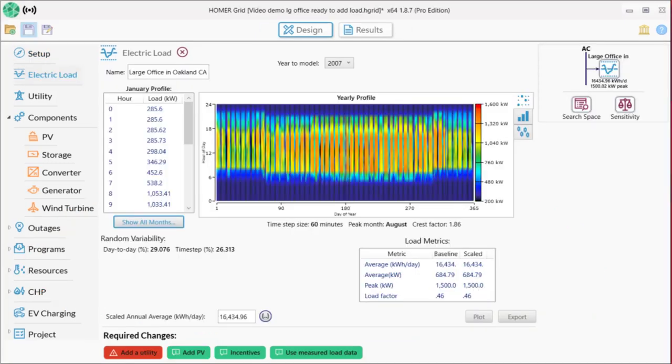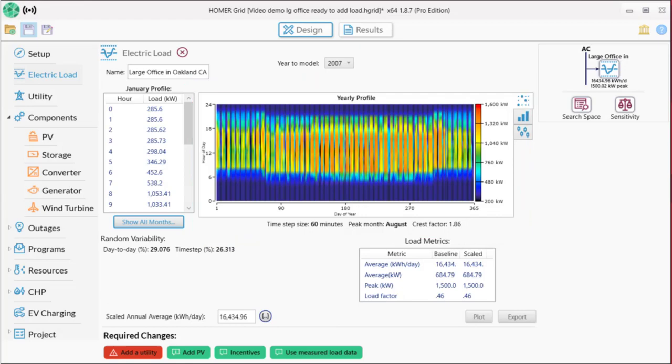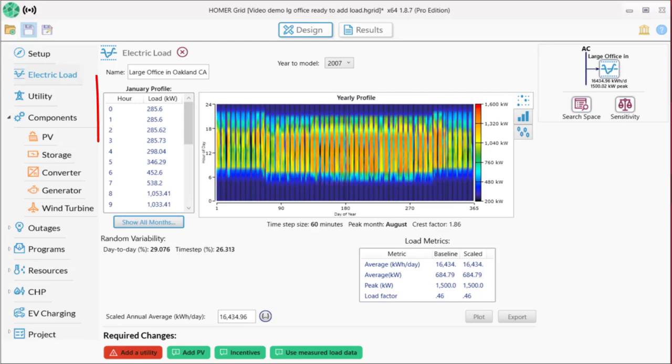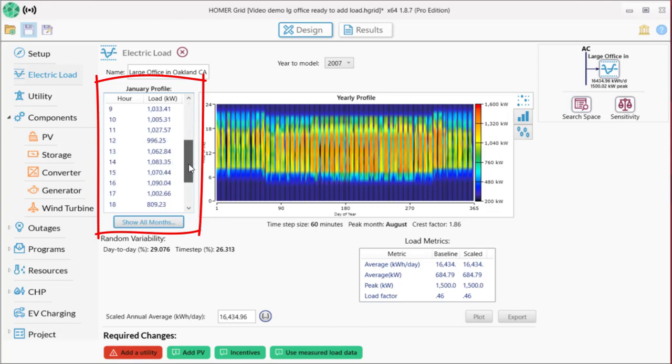We'll cover loads in a later video, but I want to point out some highlights here. The heat map in the middle of the page is a visualization of the load for the entire year. This load has an average daily usage of 16,434 kilowatt hours, a peak of 1500 kilowatts, and is highest in August, probably due to air conditioning usage. The column of numbers to the left of the heat map are the hourly averages for one month. Because this is an office building, the load is lowest at night and then peaks during the day when people are at work.